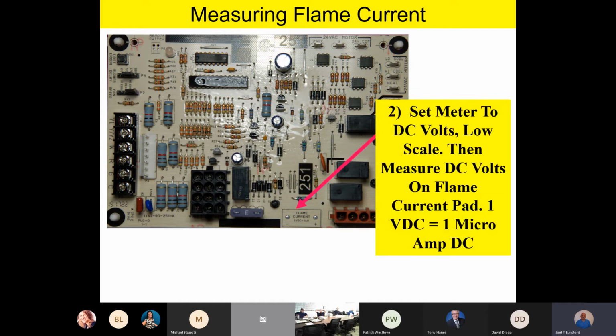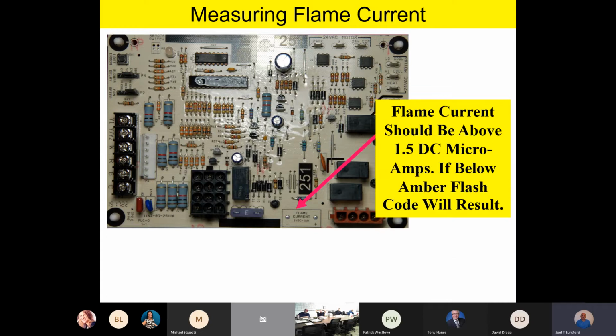Then we're going to take our voltmeter and set it to DC volts, go down to our flame current pad, and read the DC voltage between those two little points. Remember, team, 1 volt DC on your meter is equal to 1 microamp DC flame current. The flame current should be above 1.5 microamps. If it's below 1.5, the furnace will still continue to run. However, we'll generate an amber flash code indicating low flame current.